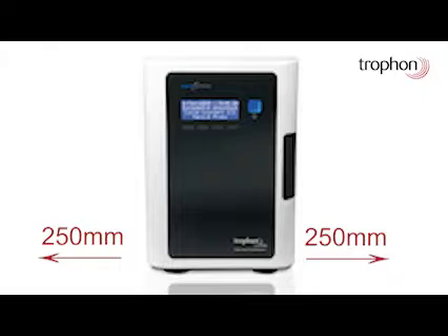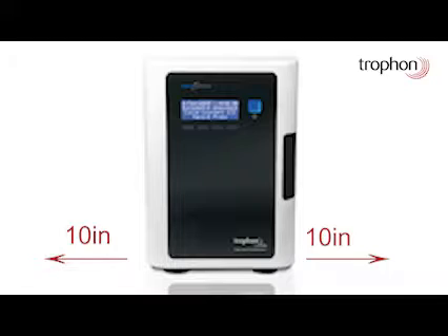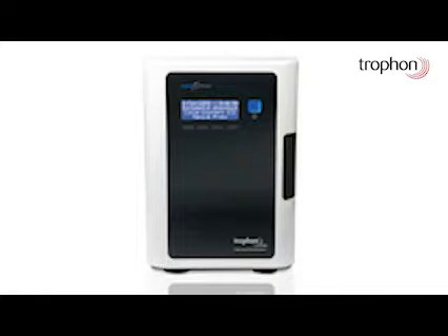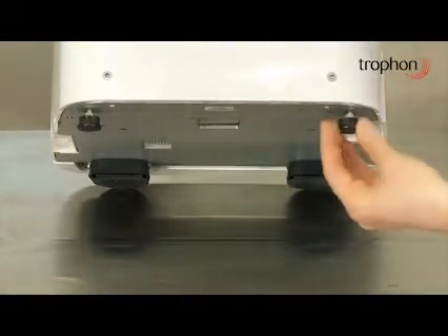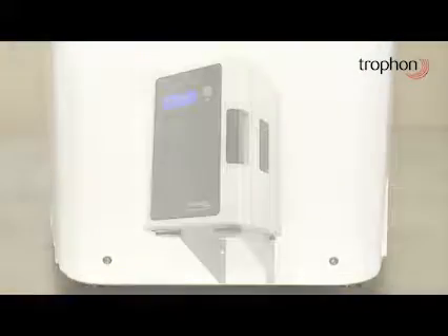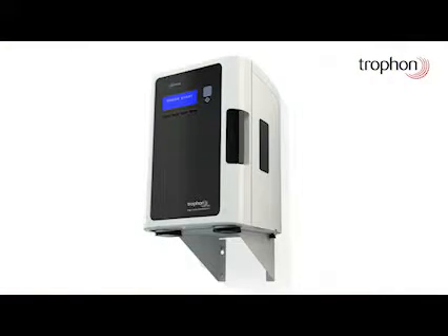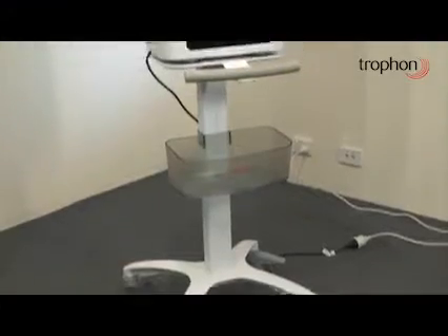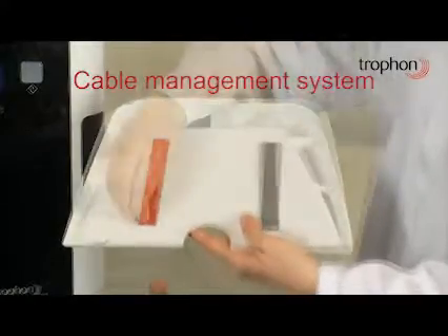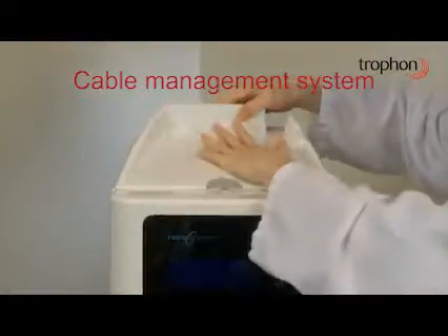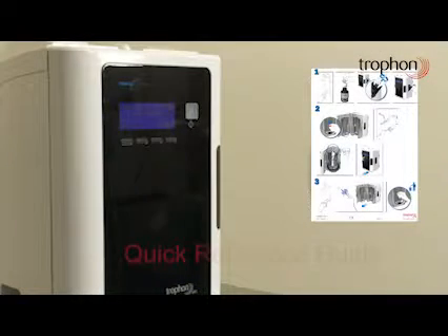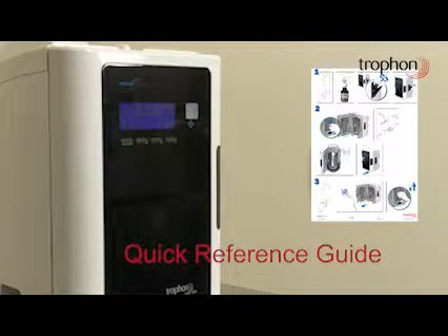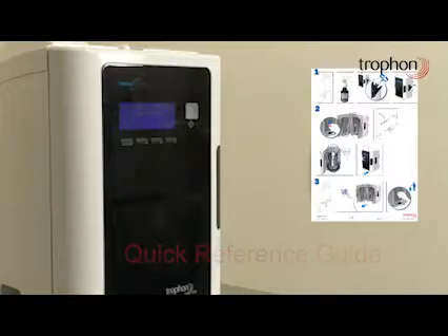Ensure that your Trophon EPR has at least 250 millimeters or 10 inches operating space beside the device. Your device should be leveled to ensure operational accuracy. You may adjust the level of your device by rotating the feet of the unit. Alternatively, your Trophon EPR can be wall-mounted or placed onto the Trophon cart. Assemble the cable management system and secure it in place. The quick reference guide provided should be fixed in a prominent position as close to the device as possible.